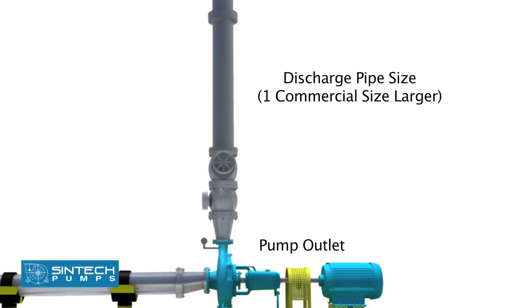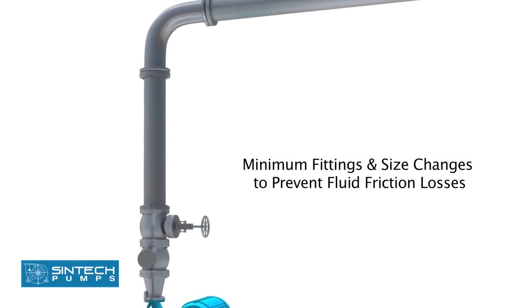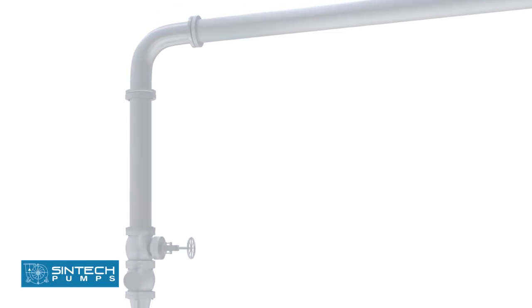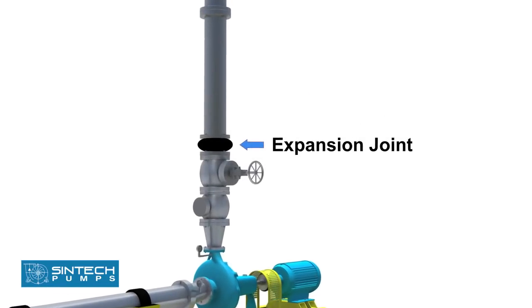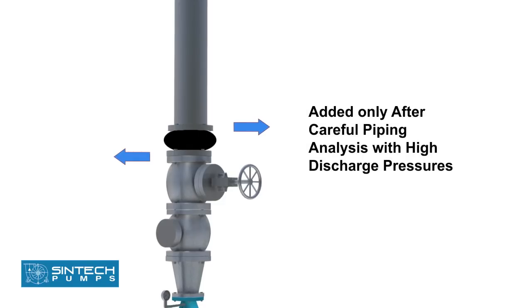Discharge pipe size should be at least one commercial size larger than the opening of the pump outlet. The number of fittings and size changes should be minimum to prevent fluid friction losses. Expansion joints may be used only after a careful piping analysis, especially when the discharge pressures are on the higher side.